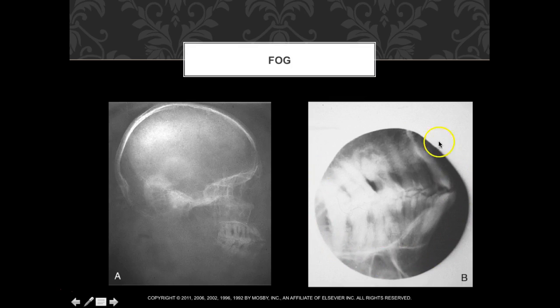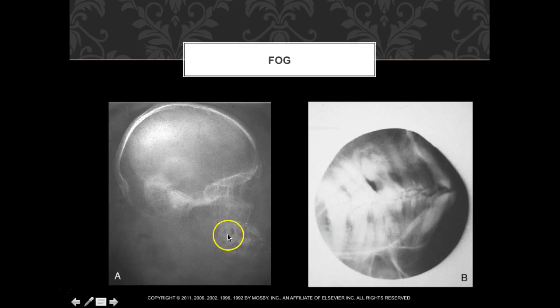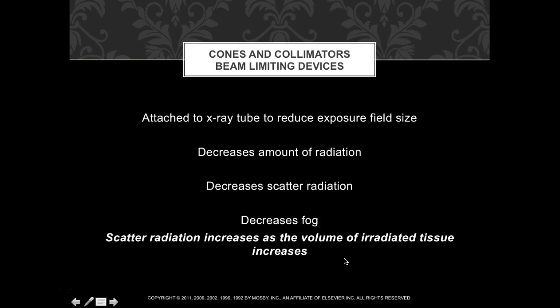Using a cone or collimator (beam-limiting device) reduces fog. Collimating tightly allows visualization of fine lines needed to identify fractures — comparing a fogged image to one taken with a cone shows dramatically better detail. Cones attach to the x-ray tube to reduce exposure field size, decreasing both total radiation and scatter radiation, which reduces fog. Scatter radiation and fog are used largely interchangeably.